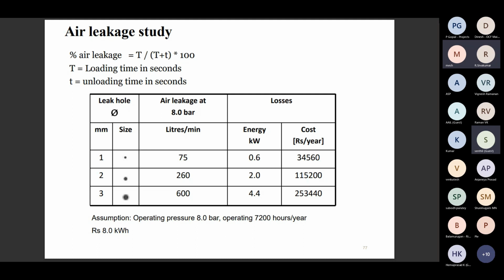That is for a single point. A 3 mm hole size, almost 10 such leaks, is typical in a factory. So imagine how much they are losing due to these air leakages. To calculate the air leakage, you have to measure the loading time and the unloading time, and put the values in the formula T divided by T plus t, where T is the loading time and t is the unloading time.